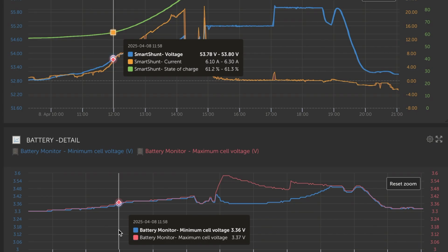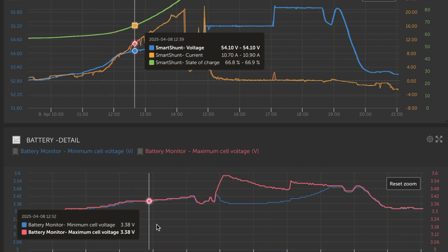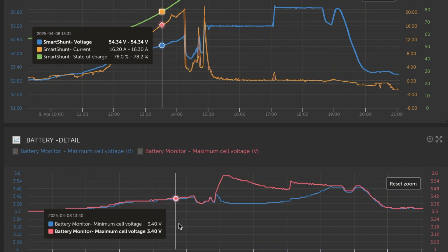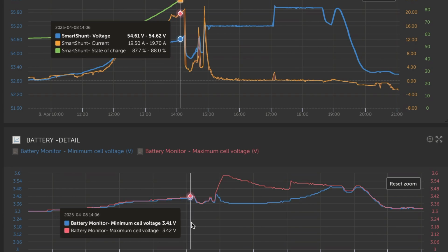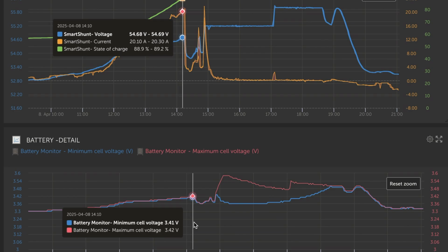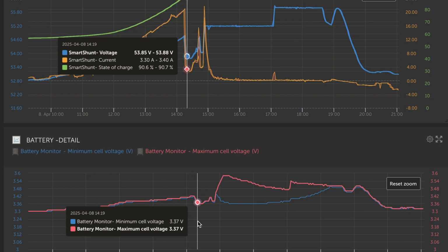They get a higher voltage than the others in a very short period of time. Here on the graph, you can see with the red line that one of the cells has a very abrupt change in voltage, which for me is a problem because the BMS signals the end of charge and starts balancing the cells.